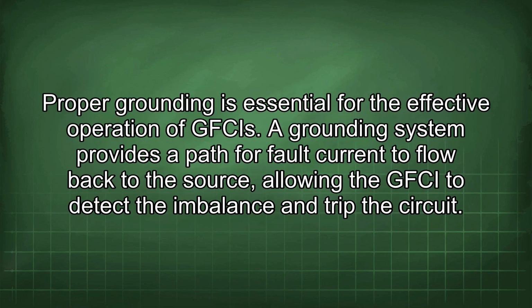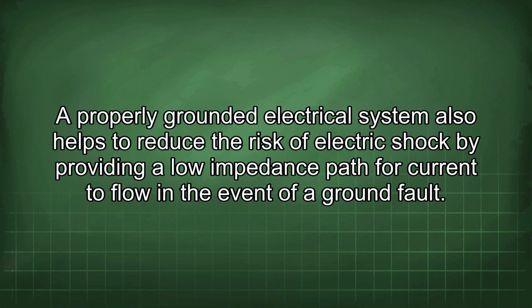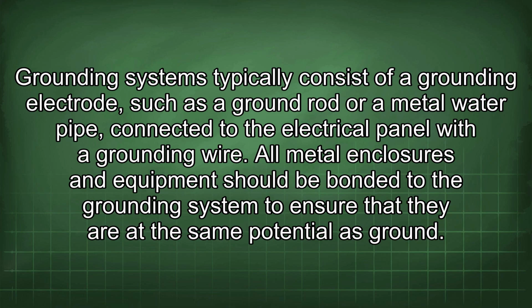Proper grounding is essential for the effective operation of GFCIs. The grounding system provides a path for fault current to flow back to the source, allowing the GFCI to detect the imbalance and trip the circuit. A properly grounded electrical system also helps to reduce the risk of electric shock by providing a low impedance path for current to flow in the event of a ground fault. Grounding systems typically consist of a grounding electrode, such as a ground rod or a metal water pipe, connected to the electrical panel with a grounding wire.